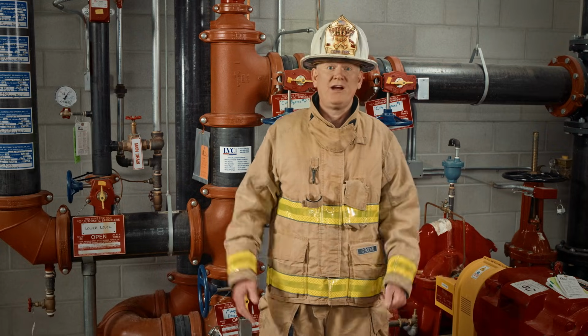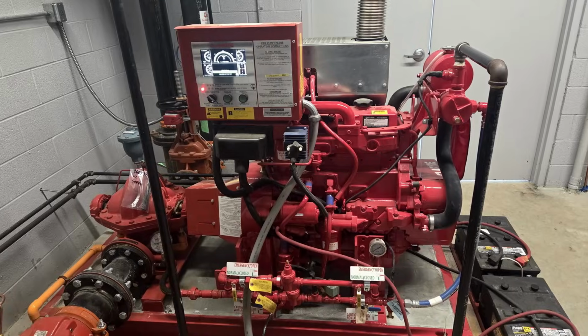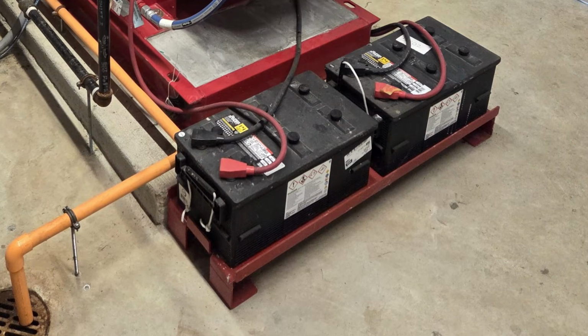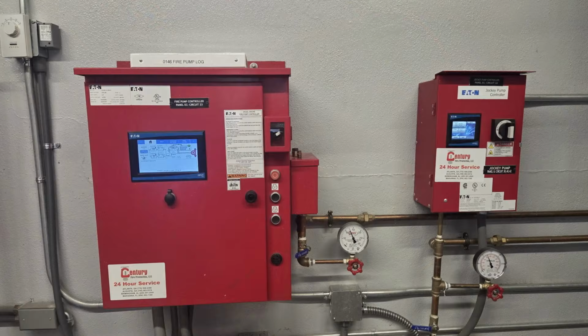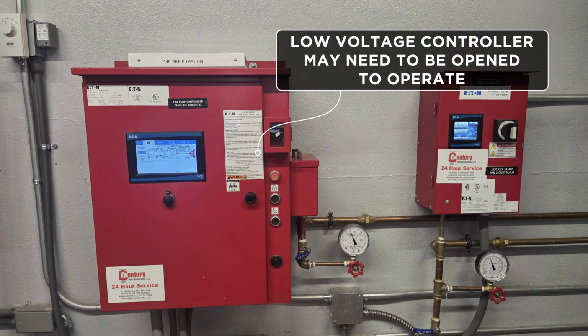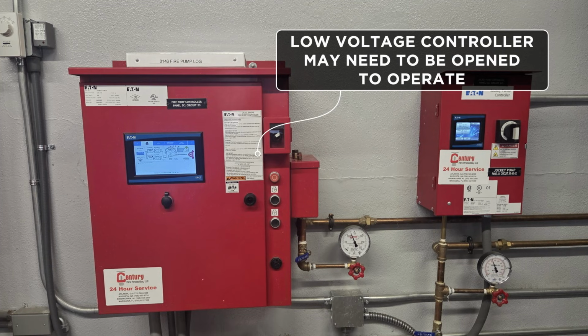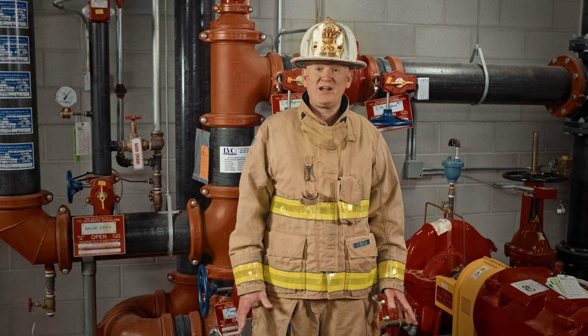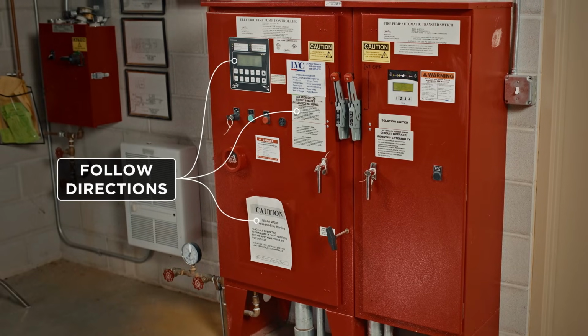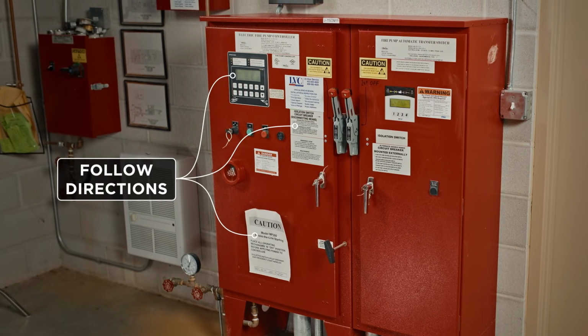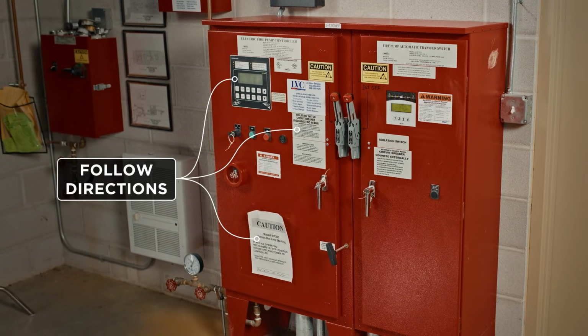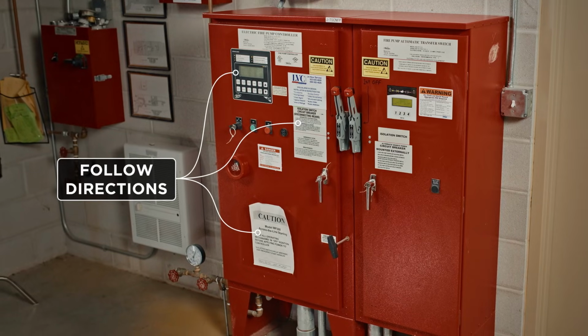The other primary driver we find are diesel-driven fire pumps. They use batteries to start the engine, similar to your vehicle. Those are going to be low voltage controllers and may need to be open to operate the pump. If you're not sure what to do, follow the directions. The directions for how to operate the controllers will be on the door. You can never go wrong just following the directions that you see on the door.